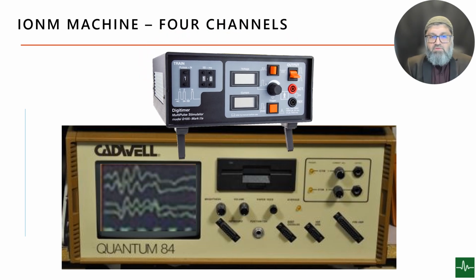Later, in the early 2000s, a device was approved by the FDA called the Digitimer, a British device. Then they had the Digitimer 100, then the Digitimer 150, and more sophisticated ones. This was the first device approved by the FDA for motor evoked potentials, and it was placed on top of Cadwell and sometimes other machines: Medtronic, Cadwell, Bravo, Endeavor and Excel-Tech. All these machines were not approved by the FDA at that time.